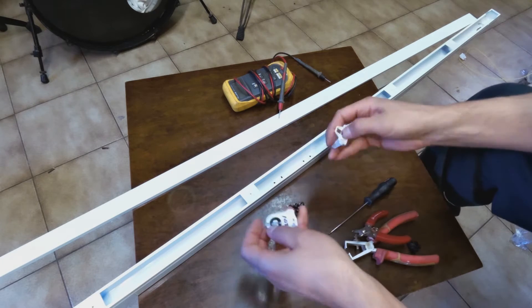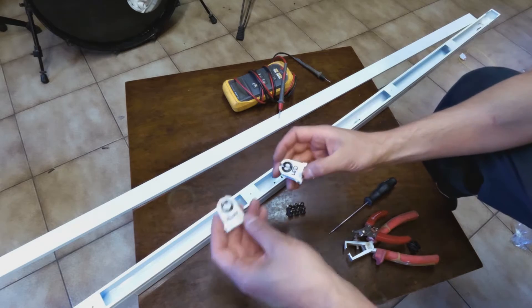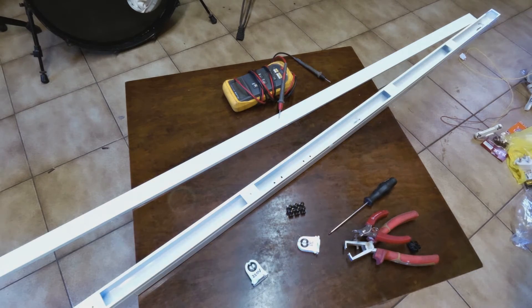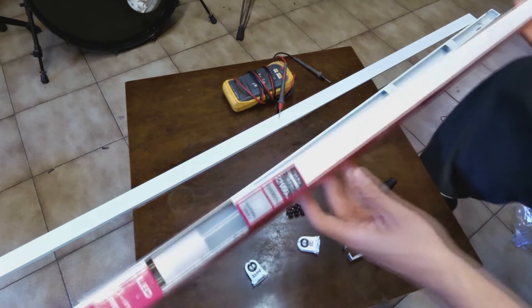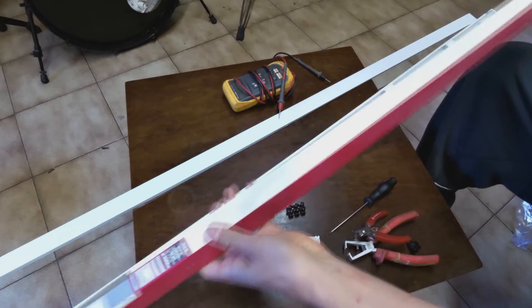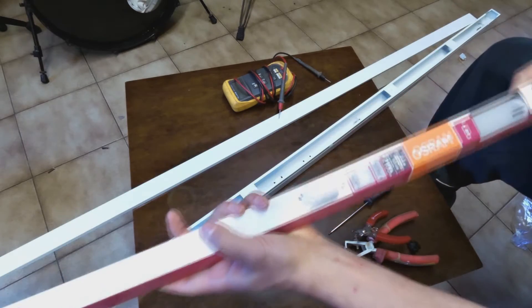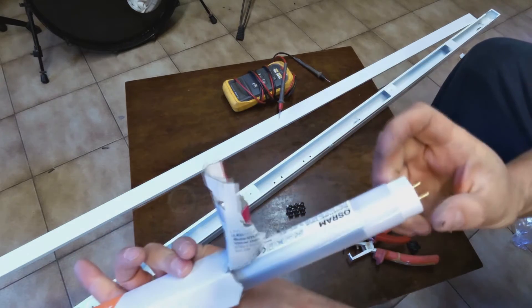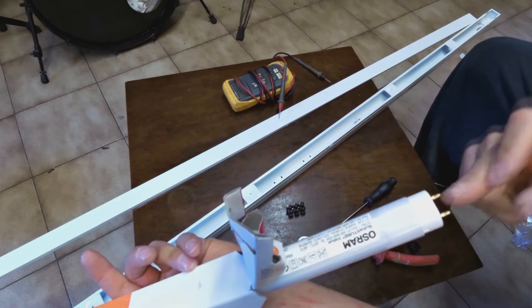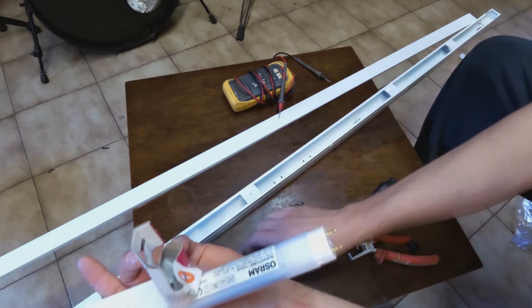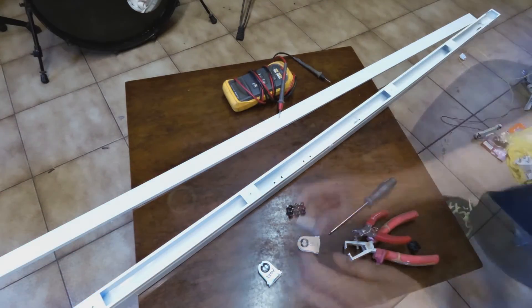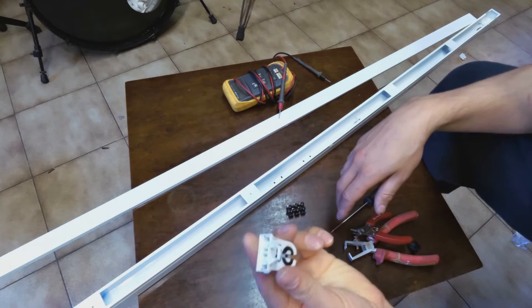Now for LED tubes you only need power on one side of the tube. For example, here I have an Osram globe and you'll see that only one side is actually requiring power. The other side is actually just a dummy. So we only need to wire the supply to the one fitting, so that's why this is actually going to be really quick.